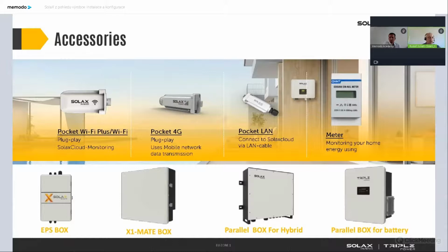It's an automatic switching in less than one second, for example. But of course, you need to stay within the limits of the inverter. So for example, a 10 kilowatt hybrid inverter can only cover 10 kilowatt of energy demand in the house in case of EPS mode or blackout. If you need more power, then you need to install a second inverter, for example, or install more batteries. But with the SolaX hybrid inverter systems, we have one of the most powerful systems on the market, so the EPS power is already very high, but of course limited by the inverter power.